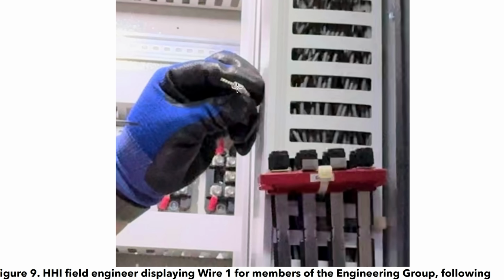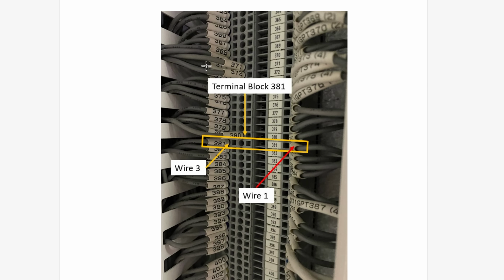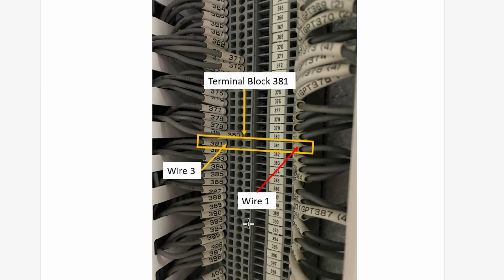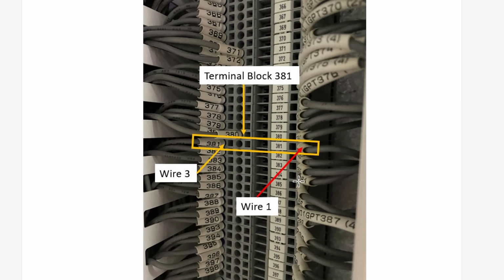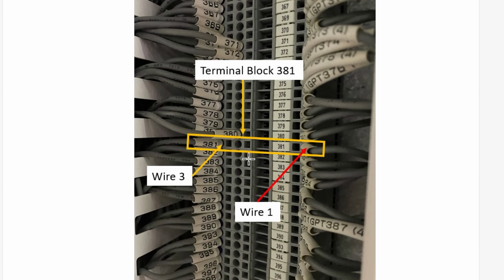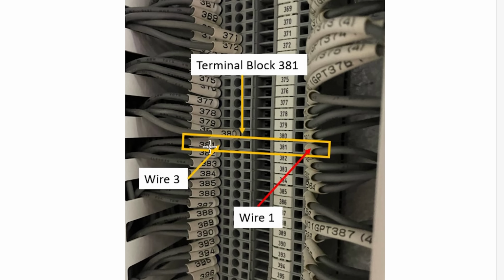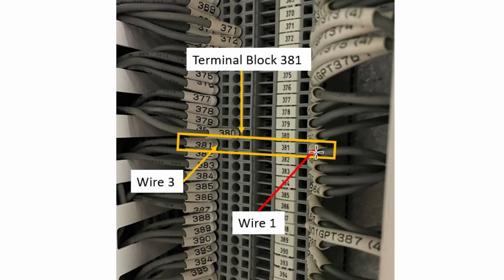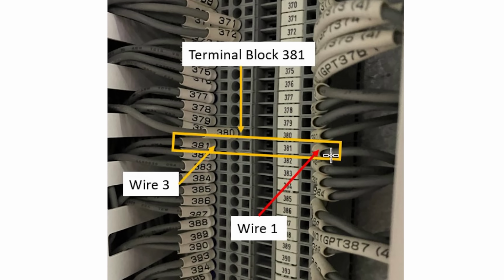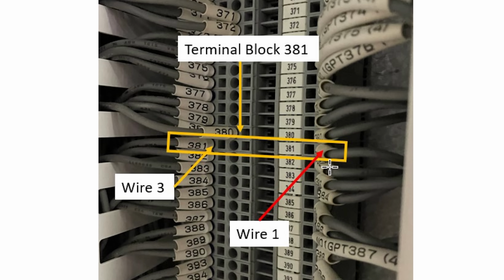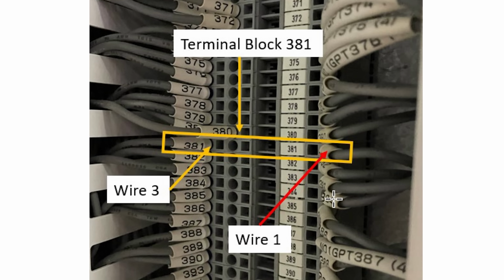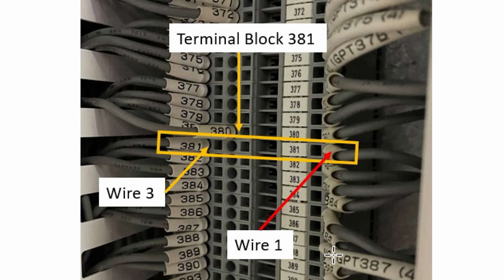There's an engineer holding the wire that was pulled out, wire 1, out of terminal block 381. On the DIN rack, here's all of the Wago terminal blocks, one after another, and here it is, 381. There's wire 3 on the left side, wire 1 on the right side. This was the culprit. I wish they had gotten a better angle to see side by side how it looks compared to all the other ones. But it makes you wonder how many of them didn't make it there.